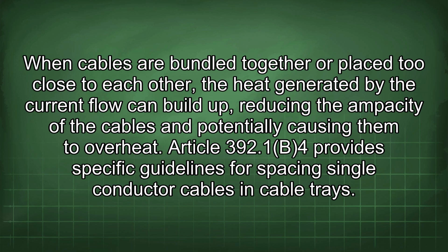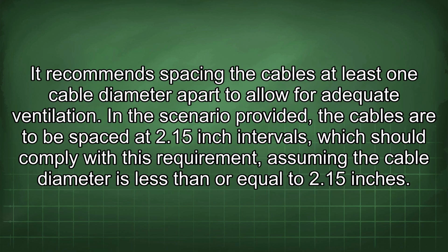Article 392.1b4 provides specific guidelines for spacing single conductor cables in cable trays. It recommends spacing the cables at least 1 cable diameter apart to allow for adequate ventilation. In the scenario provided, the cables are to be spaced at 2.15-inch intervals, which should comply with this requirement, assuming the cable diameter is less than or equal to 2.15 inches.